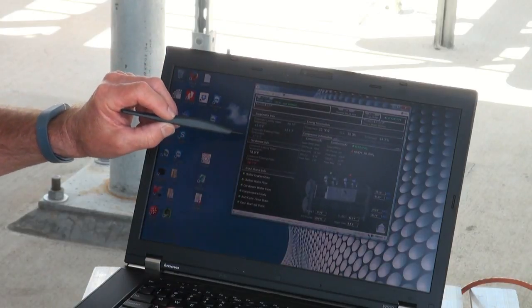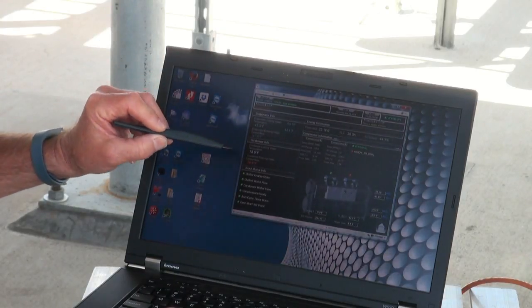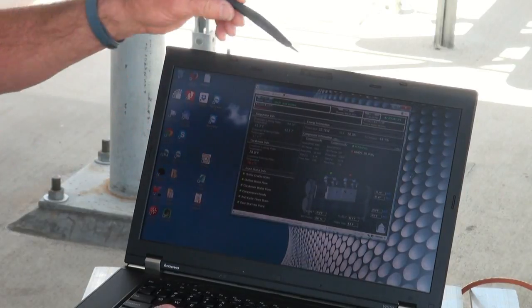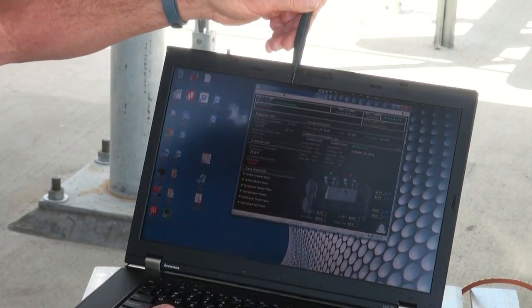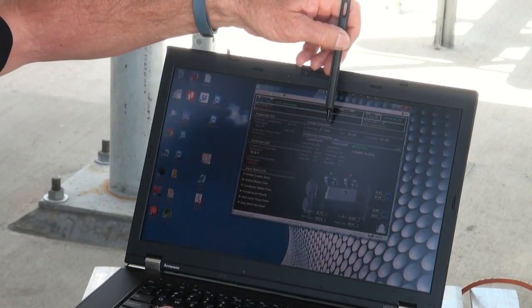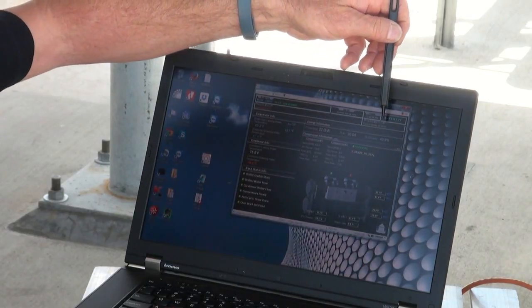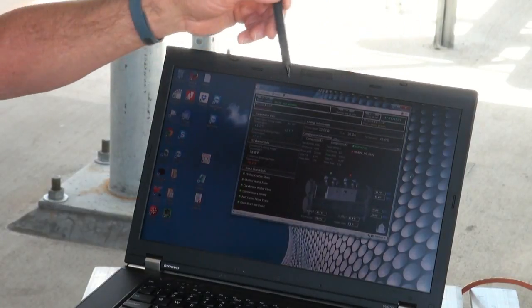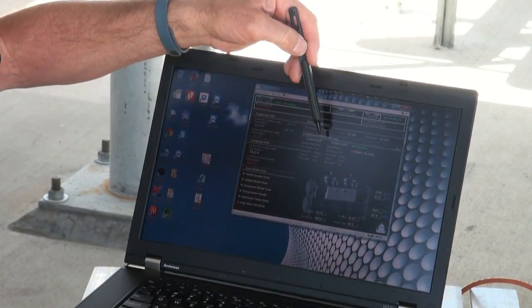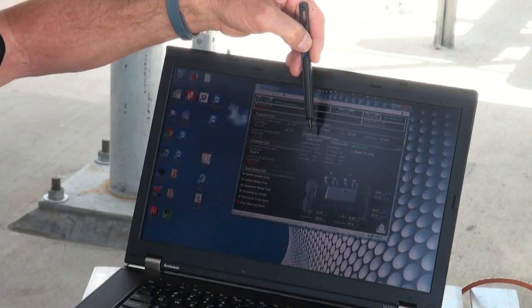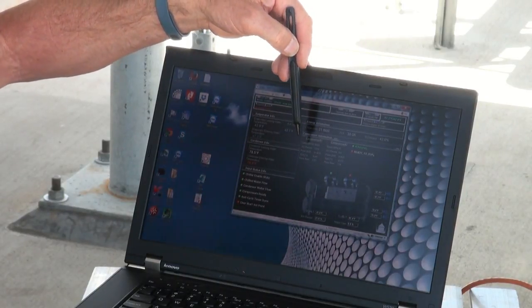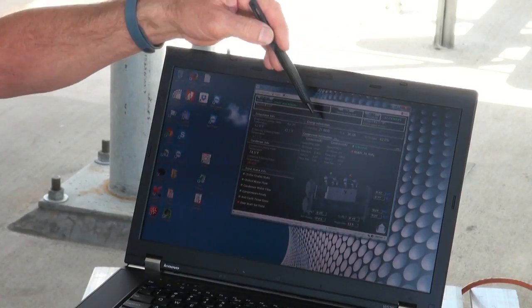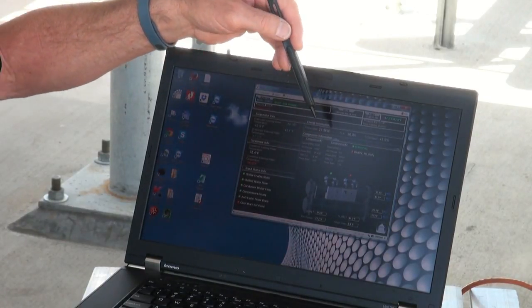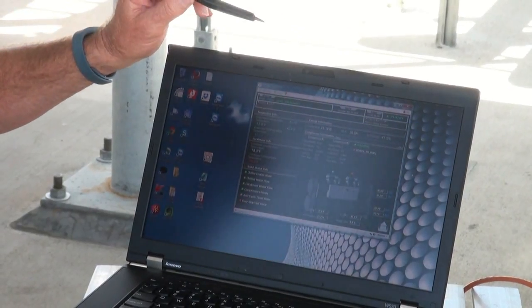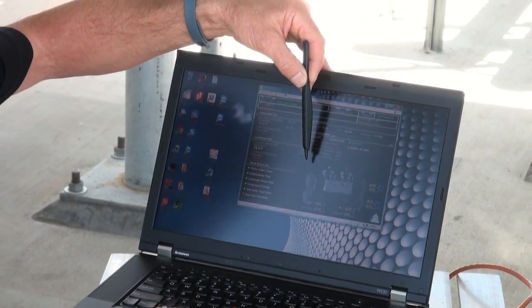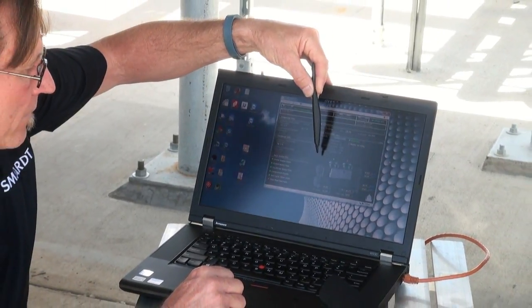We've got evaporator info, set point, entering and leaving, condenser info, entering and leaving. We've got our power input, where we're showing full load amps and percent demand. We've got a little bit of information on compressors 1 and 2, including speed and IGV position. So there's a lot of information we can pull from the compressor. This is just a little snippet of what we can pull. And then you've got the graph of the chiller itself.